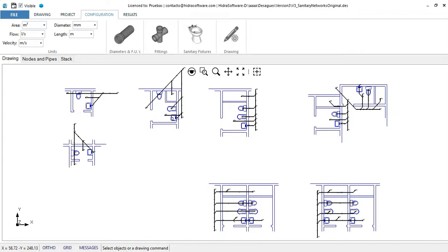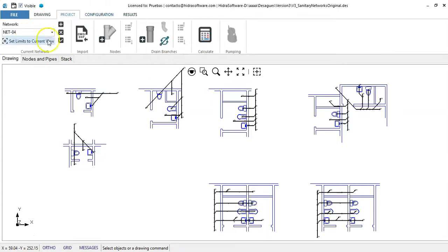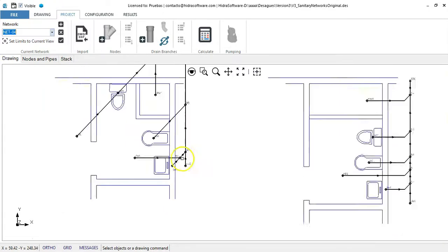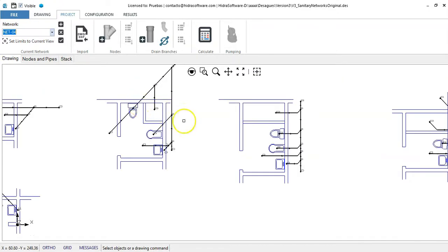Then, having already defined the vent sizing tables, we are going to see what changes are required in the horizontal drainage networks created in your projects to be able to link them, so to speak, to the respective vents networks. First, and as what, in our opinion, is recommended, we will propose that each sanitary fixture in the drainage networks be ventilated individually. This implies, as you know, that from each fixture or, better said, from the corresponding drain pipe, there must be a connection to one vent pipe.